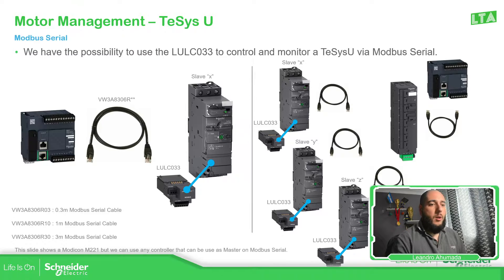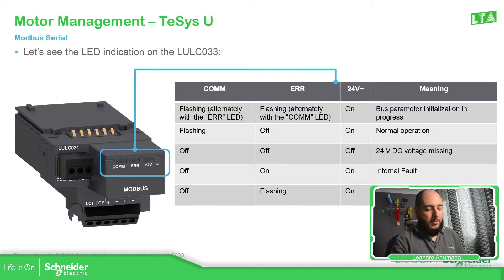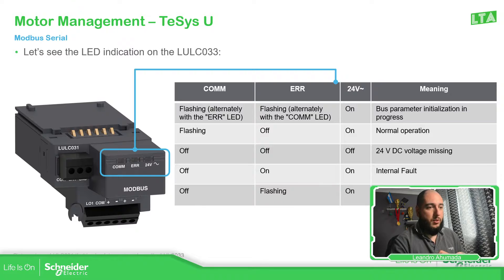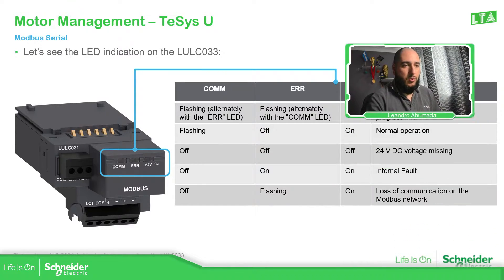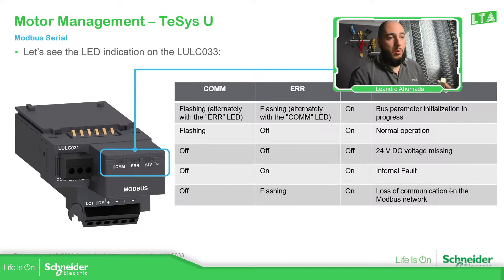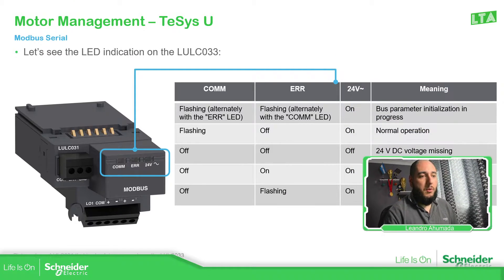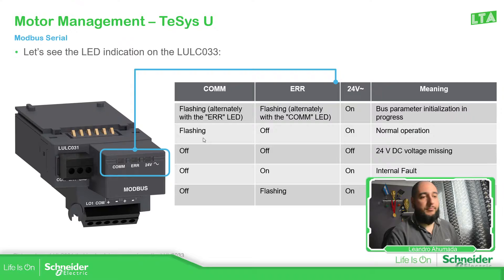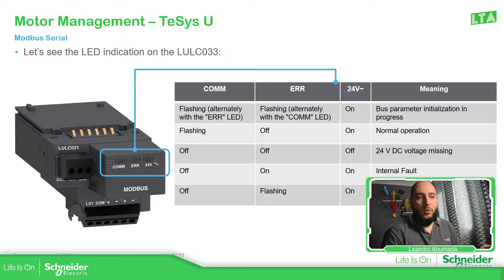Once you have that configuration and you connect the device, you should be able to see on the front that we have three LEDs. These three LEDs give us information about what's going on with the unit. So basically, if you have the middle one — which is for error — flashing and you don't have communication, you know there is a communication loss on the Modbus network. If everything is well, you should have the communication LED flashing and the 24-volt LED on.